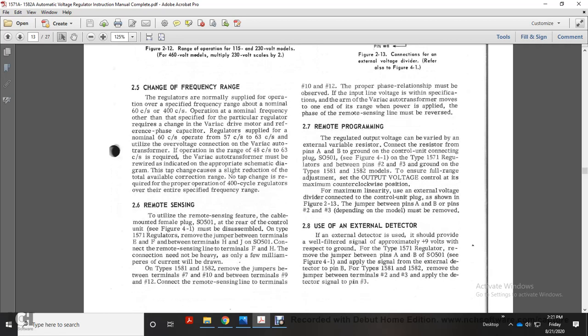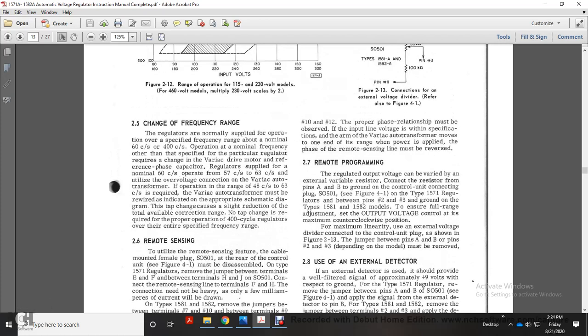2.6, remote sensing. To utilize the remote sensing feature, use a cable that mounts a female plug with the SO501 at the rear of the control of the unit. Figure 4.1 must be disassembled on the Type 1571 regulators. Remove the jumper between terminals E and F, and between terminals H and J of the SO501. Connect the remote sensing line to terminals F and H. The connection need not be heavy, as only a few milliamperes of current will be drawn. On Type 1581 and 1582, remove the jumpers between terminals 7 and 10 and between terminals 9 and 12. Connect the remote sensing line to terminals 9 and 12.